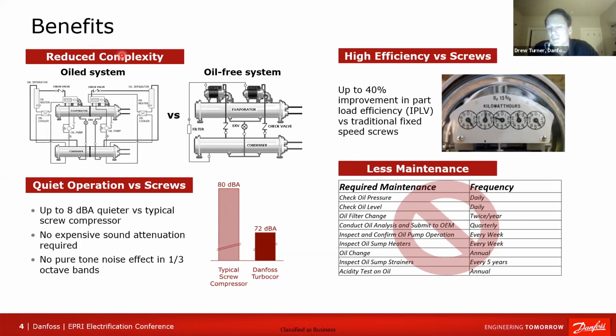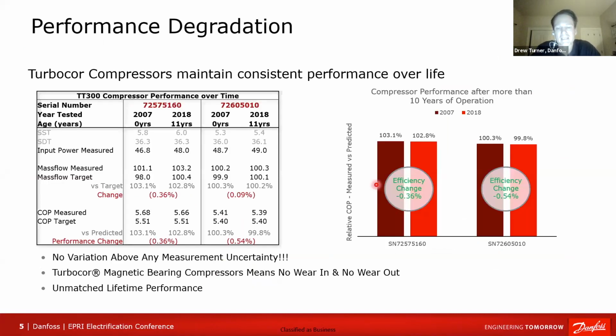So it's significantly quieter and significantly less maintenance. The reduced complexity is the main driver for that. If you have no oil system to maintain, then you have no maintenance of that system. The other benefit that came from this, that he didn't really recognize was even an issue at the time, but has become recognized as a significant issue today because of the instrumentation and tracking of all the existing HVAC systems out there, is that performance degrades over time. And the 2 main drivers of that performance degradation are the same ones that I was talking about that drove the noise levels.